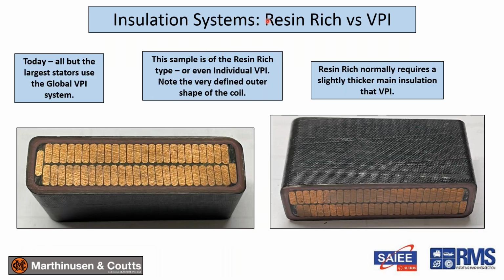Okay, then that's the same sample as earlier, just showing you it from the side. If you look at how accurate the external dimensions of this coil section are, this is a resin-rich sample, meaning it is pre-formed before it goes into the stator, and that's quite different from most modern machines, which are of the global VPI type.